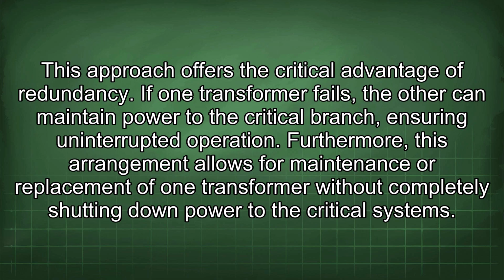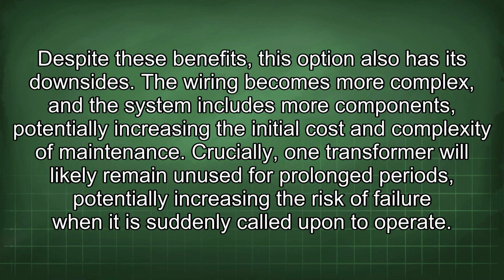This approach offers the critical advantage of redundancy. If one transformer fails, the other can maintain power to the critical branch, ensuring uninterrupted operation. Furthermore, this arrangement allows for maintenance or replacement of one transformer without completely shutting down power to the critical systems. Despite these benefits, this option also has its downsides. The wiring becomes more complex, and the system includes more components, potentially increasing the initial cost and complexity of maintenance.